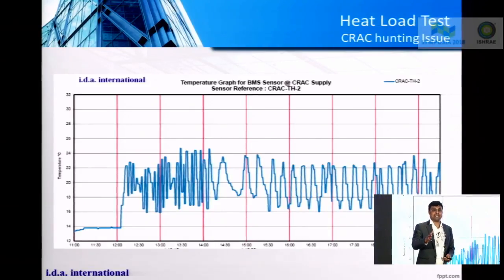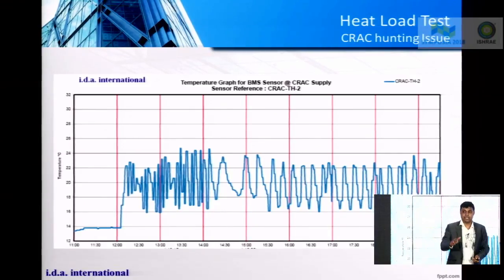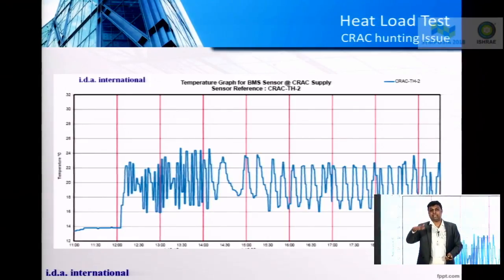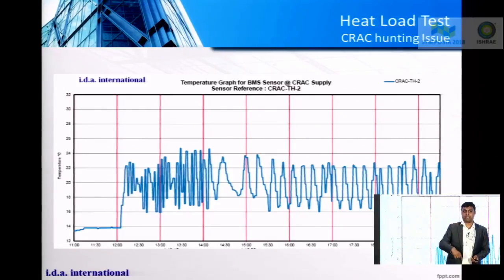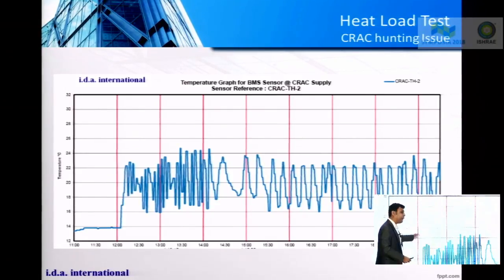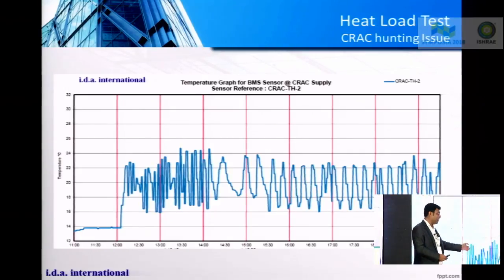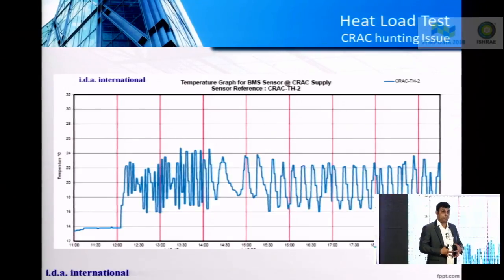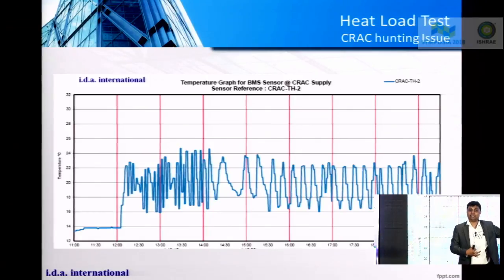This issue is called CRAC hunting, which means the chill water valve is not steady. It continuously fluctuates and modulates the chill water temperature, which in turn modulates the air temperature. So you could see a frequent rise and drop in the temperature of the CRAC units, and this temperature is reflected in your cold aisle containment as well.